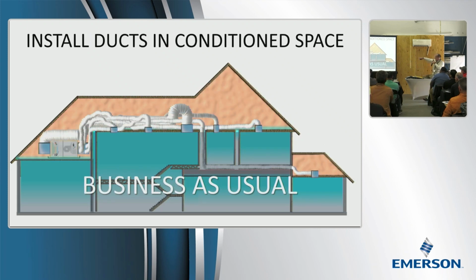You can do the big crappy spaghetti duct, lay it all on the ceiling, do whatever you want when you foam it, and you'll get away with it. As a matter of fact, I have never seen an encapsulated space, unless it had leaks in it, with sweaty ducts. You can get away with really, really bad ductwork, which is a good thing because crappy ductwork is extremely popular. It's everywhere, we can't keep it on the shelf.